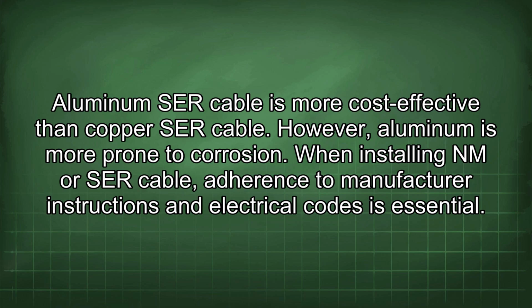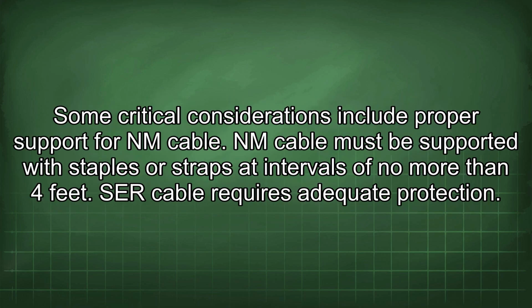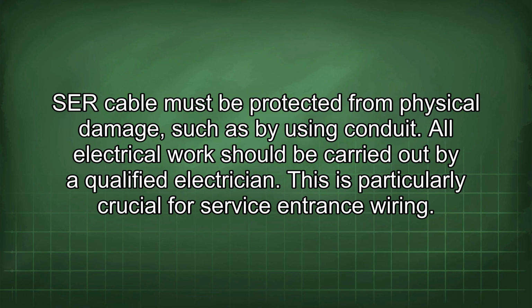When installing NM or SER cable, adherence to manufacturer instructions and electrical codes is essential. Some critical considerations include proper support for NM cable. NM cable must be supported with staples or straps at intervals of no more than 4 feet. SER cable requires adequate protection. SER cable must be protected from physical damage, such as by using conduit. All electrical work should be carried out by a qualified electrician. This is particularly crucial for service entrance wiring.